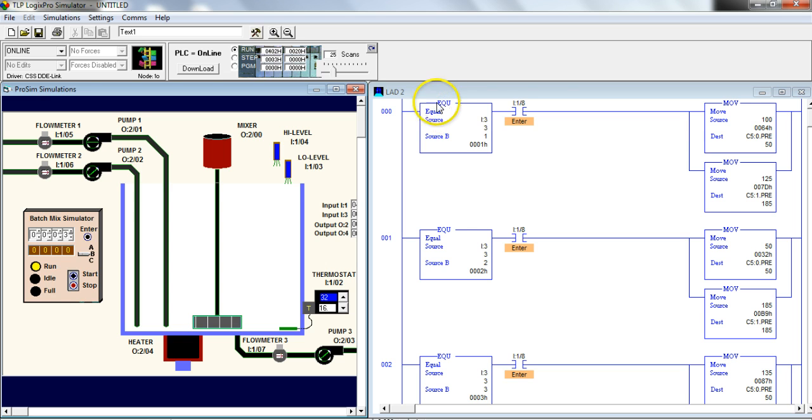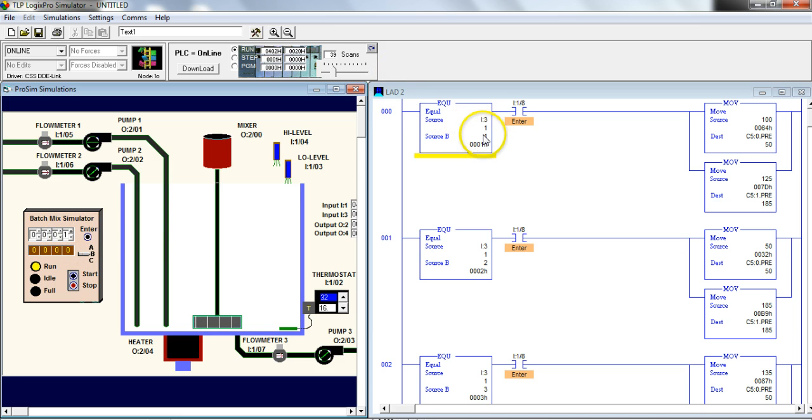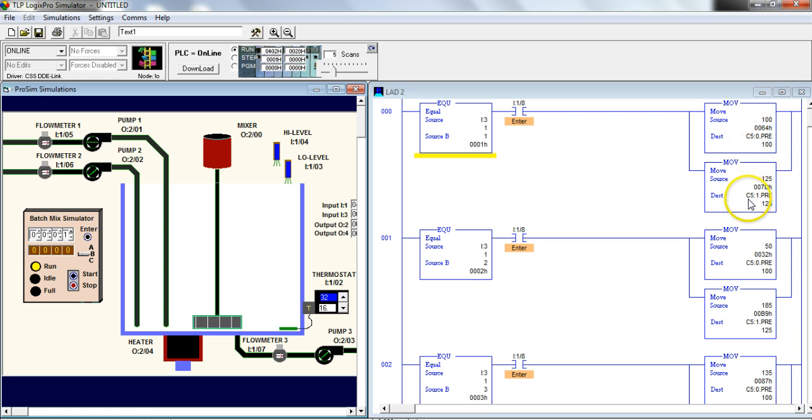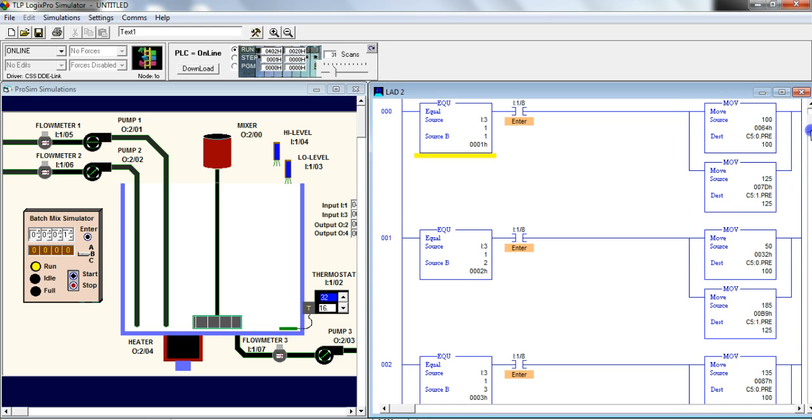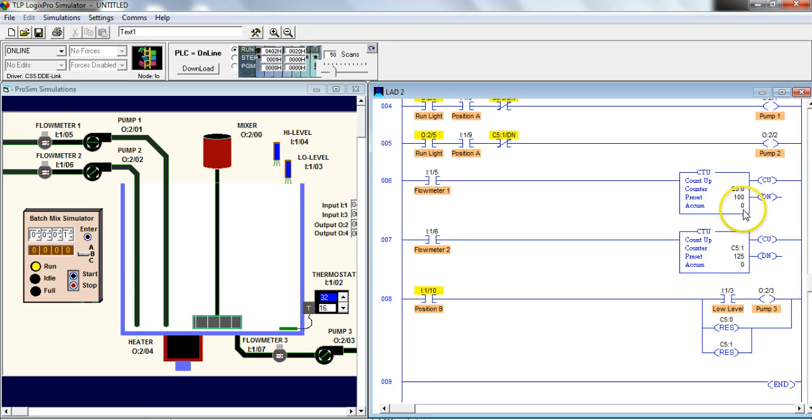And if you look at here, here's an equal instruction. I'm just using that because if you look at, if I go to a 1 here, now this is true because my little thumb wheel is set to 1 and it equals 1. So 1 equals 1. If I push enter, I'm going to execute these two moves right here. So if you look at that, you'll see the equal instruction is true. I pushed enter, so that's true. Now if I go down and I find my counter 5-0 and my counter 5-1, I should have a 100 and a 125 in their presets. And they happen to be down here farther. And there they are, 100 and 125 in the preset.